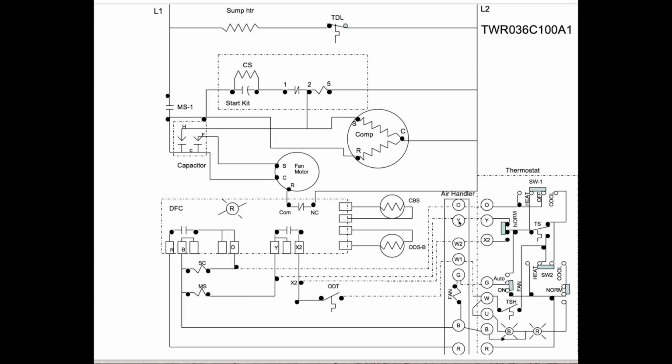On a call for heat, we're going to energize Y. Now, why, you say? Well, hold it, we're energizing Y for cooling. No, Y, if you follow Y through, it goes here, through the field wiring, comes over to here and energizes the main switch or contactor. This is Trane. They have their own little words for everything. So it'll energize whether it's heat or cool.